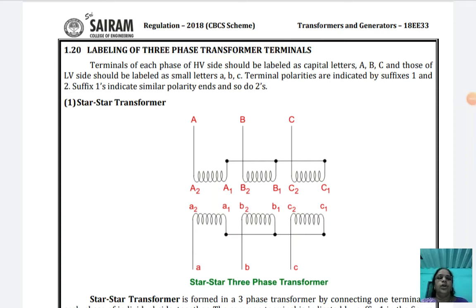Dear students, now I give a lecture on labeling of three-phase transformer terminals. Transformer terminal marking is very important for the polarity test of three-phase transformers or single-phase transformers, because if the polarity changes, we can't synchronize two transformers. That is true particularly for three-phase transformers, and for single-phase transformers also. The labeling is very important for transformer terminal marking.